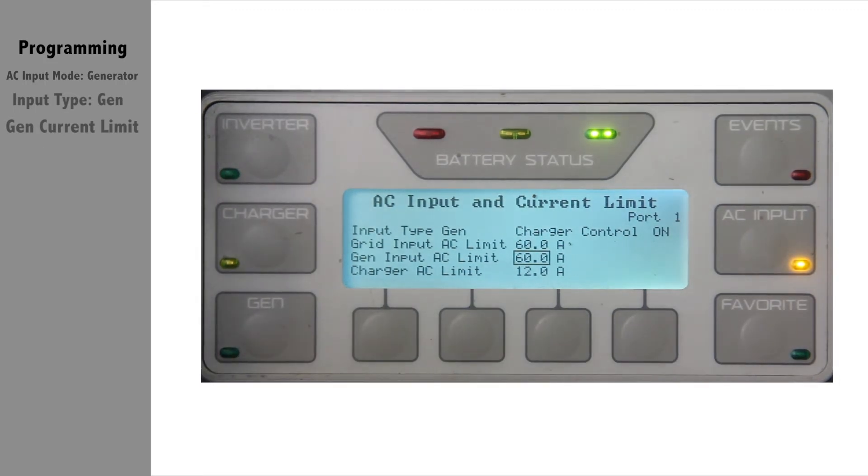Next up is your charger current. This has to be greater than zero for the charger to activate. Set this no greater than your recommended max charge current per your battery manufacturer.